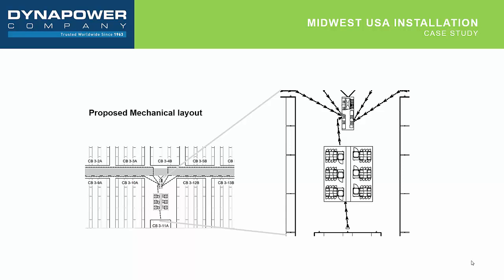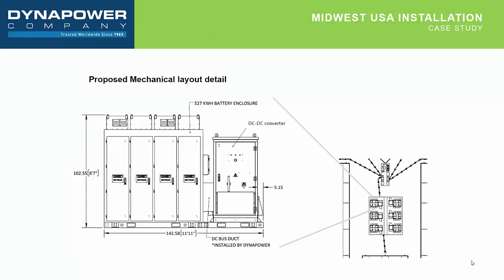As we jump to the next slide, we see a little bit more breakout here. On the left, you'll see what that DC storage system would actually look like. In this case, it's a skid-mounted system. On the right of the skid is the DC-DC converter. To the left is the storage enclosure. So this is an example where there was plenty of room, plenty of spacing, so there was no shading, and a very good fit systematically for a retrofit application.